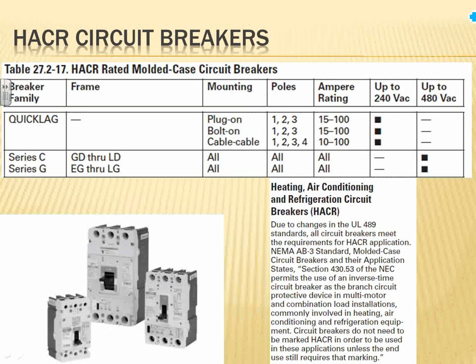Okay, HACR versus circuit breakers. I pulled this one from Cutler-Hammer. I don't know if you've seen it. Who asked about the HACR? Long story short, based on UL 489, all circuit breakers are rated to handle HVAC equipment. That's what Cutler-Hammer and Square D say, the same thing. All circuit breakers are rated.